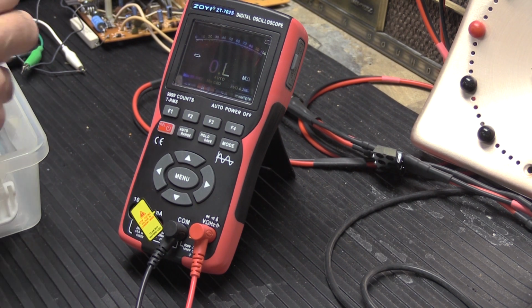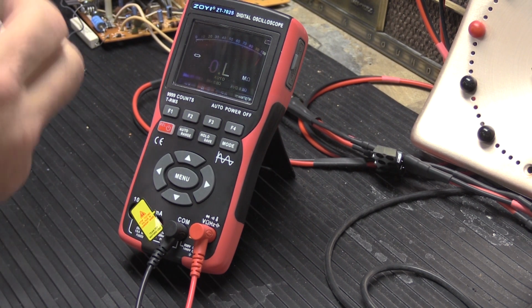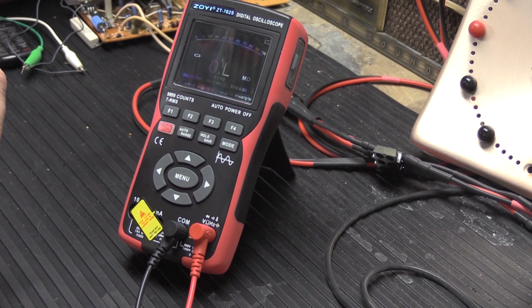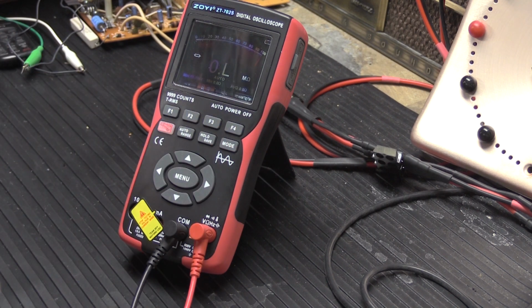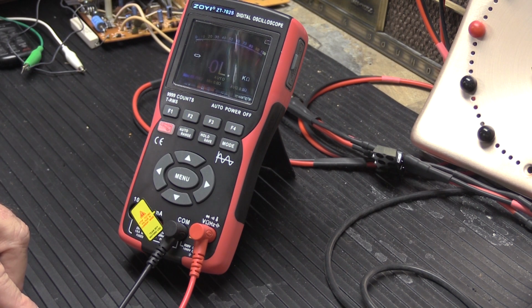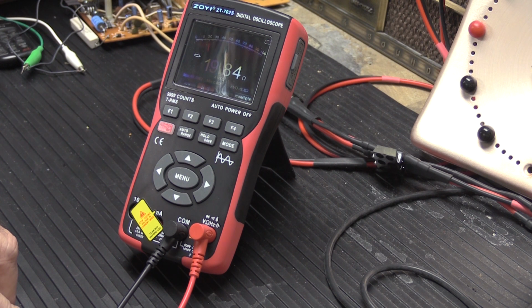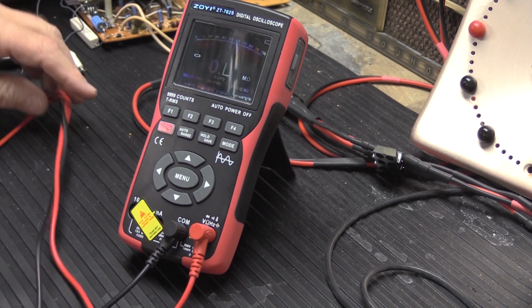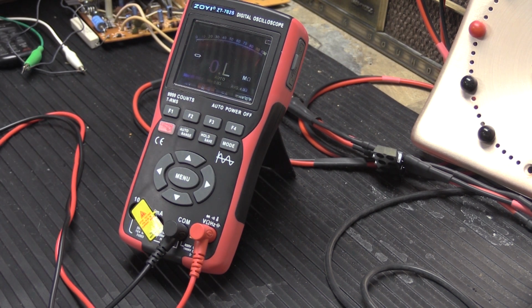If we get a bigger, higher rated resistor, here's another big old chunky one. This is a 20 ohm, 10%, 10 watt. It's a big old ceramic resistor, like a power resistor. So it's 20 ohms. So if we put this on here, it's right in there, 19, depends on how well the probe's contacted, but 19.8, it's well within specifications because it's plus or minus 10%. So it's anywhere from 18 to 22 is within tolerance, and that's pretty much what it shows. So that works really well. Also, you can also use it to check diodes.